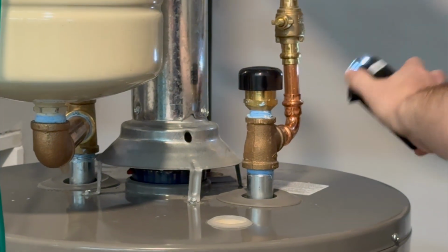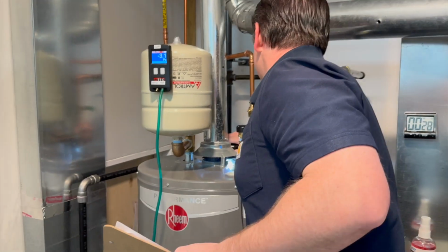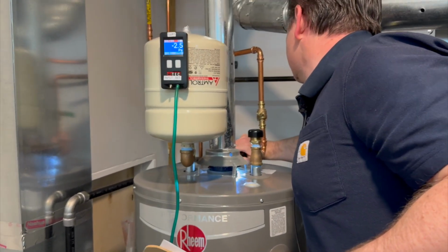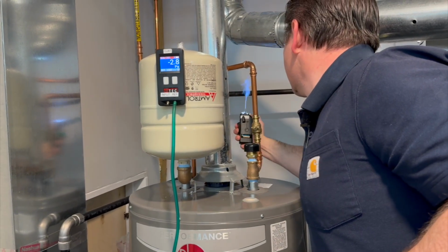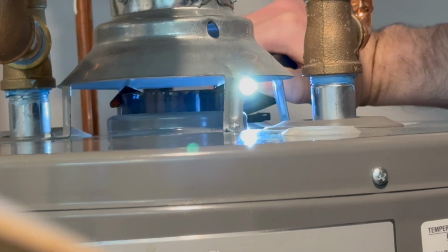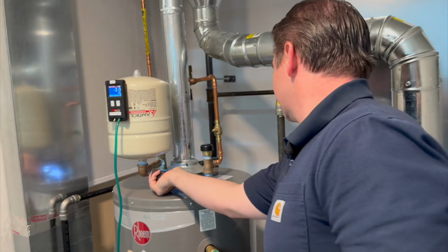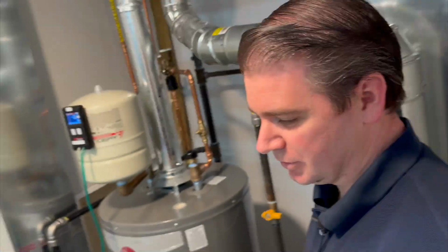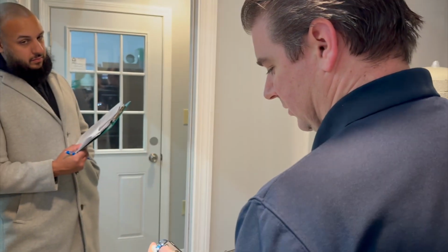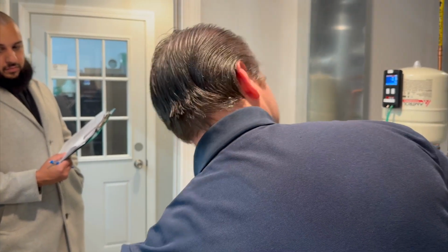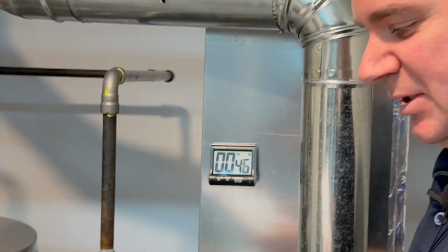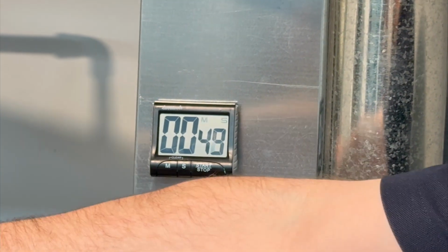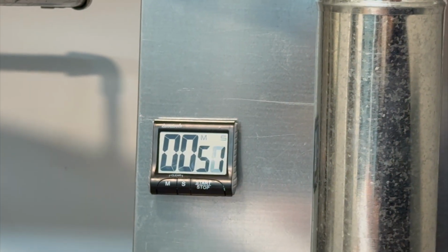Looks like the smoke's going up already. Checking the backside. Going right up. Make sure the proctor can get that on camera. Turn the light back off so we don't waste the battery. And so we pass spillage within 45 seconds. So the water heater, it passes.